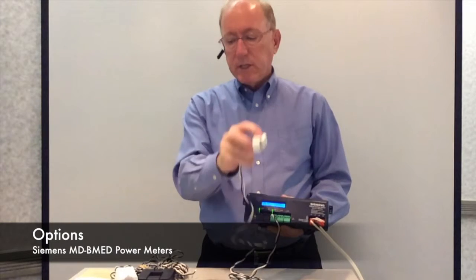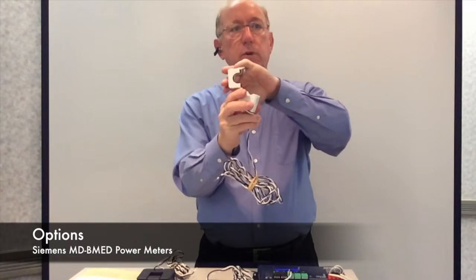The MD series power meter not only comes with the 2 meters, which are the non-display version or the display version with Ethernet, but it comes with a series of additional CTs, or current transformers. These range from 50 amps up to 4,000 amps. They include devices that are nice and small that would be used in your typical 50 and sometimes 100 amp service, more of a mini CT. They get larger with a version that can handle 100 through 200 amp. These are a hinge type of CT, which are very easy to do in an electrical panel in that you just open up, place it over the wire, and close it back down.